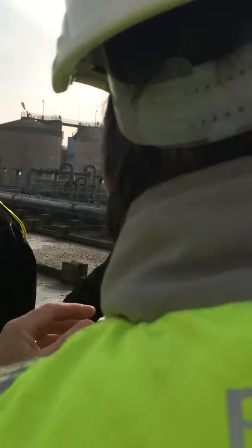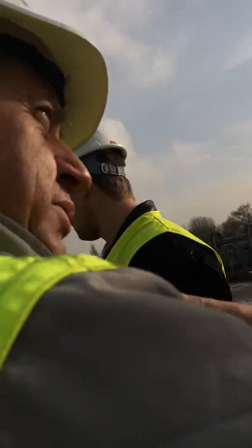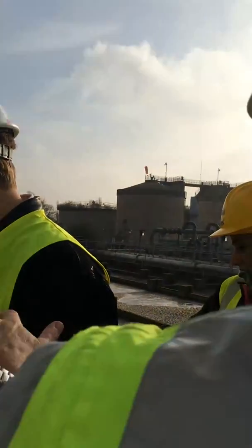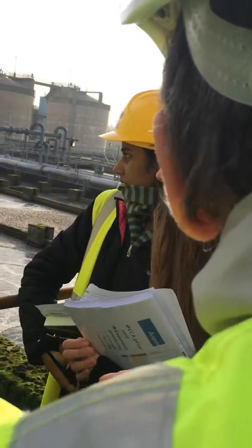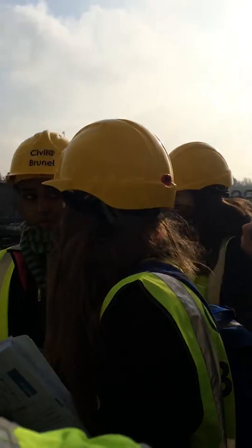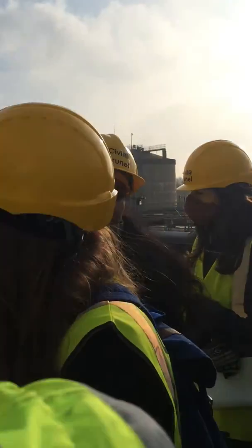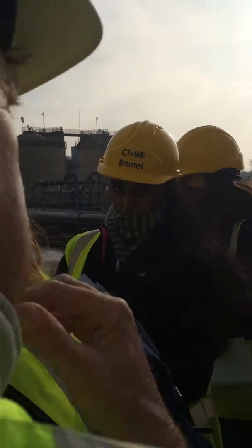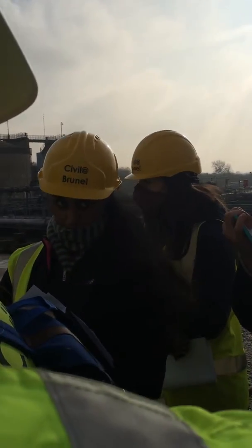They'll use oxygen exactly the same as we do. We burn calories, we breathe air, we use oxygen to break down the organics, release the energy. Ordinarily they would do that. In an anoxic zone, they haven't got oxygen available, so instead of oxygen they will now raid the nitrate and reduce the nitrate to nitrogen gas and use that as the oxidizing source.